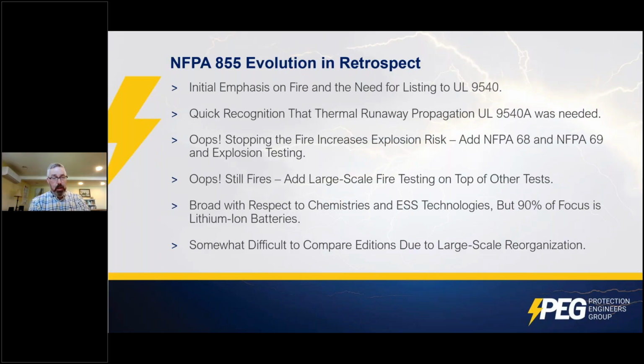Early on, they found after an event in Arizona that a fire is not the only issue. We have to worry about explosion, and that the risk, even when we put the fire out, the gases that are released are explosive. They're even more explosive when there's no fire. That drove NFPA 68 and NFPA 69, explosion control and explosion prevention, into the testing. And now they're saying, oops, they're still having large fires. Add large-scale fire testing on top of the other tests to say, even if everything really goes wrong, if this thing does catch fire, what happens? They need to know that.